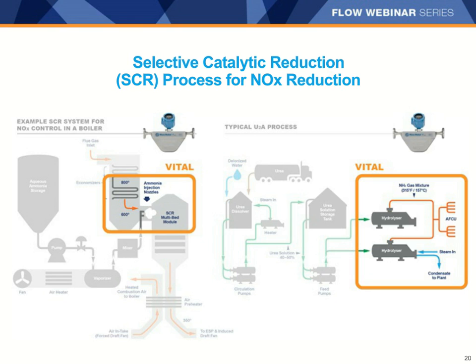Some of the challenges facing users of SCR technology are making sure that the ratio of reductant to catalyst is correct for the amount of flue gas being scrubbed. Since the stoichiometry, or chemistry, is based on mass or mole weight reactions and not volume, it is better to control using a direct mass measurement. Coriolis meters can help with mass balancing, precise mass flow measurement, reducing ammonia slip, and measuring the ammonia concentration, all in one device. In addition, due to their design, they contain no moving parts, which can improve unit reliability as well.